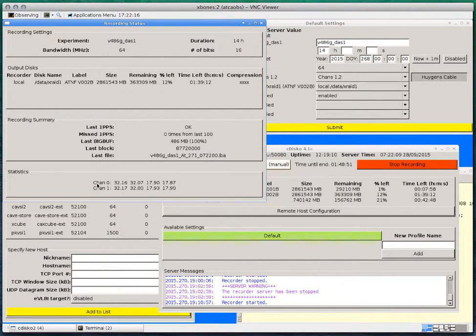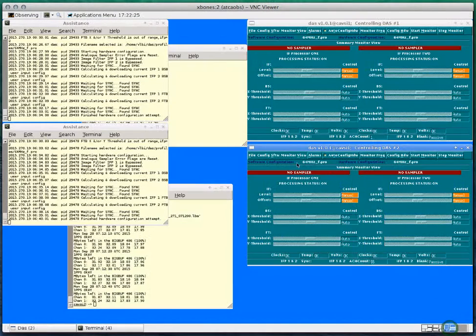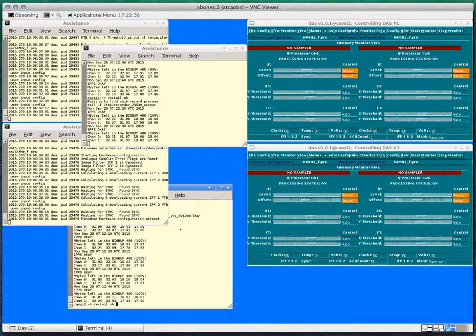You can monitor the channel sample statistics either on cdisko, on the RecMon webpage, or, as an alternative, if you log onto the recorder where the data is coming, you can run a script called rectail.sh. This updates much more quickly. cdisko and RecMon typically can have a 1 to 2 minute latency, so if you do use those, you need to make sure you watch it for quite a while.